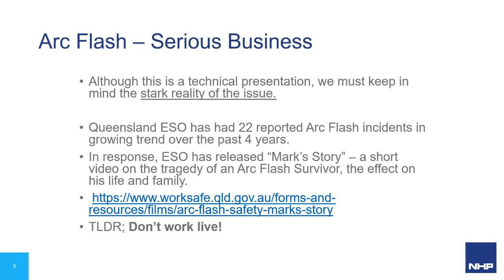It was a very avoidable incident. He was adding a power analyzer to a live switchboard. He did a lot of things wrong and he acknowledges that now, but it's not anything that we haven't seen from electricians out there in our own world. So really the message that they're pushing there is don't work live. We'll go into that in a little bit more detail later, but it is a serious issue and it does result in deaths. Queensland ESO put this together mainly because they've seen a growing increase in arc flash incidences. They've had 22 reported arc flash deaths and injuries over the last 4 years, which they're really worried about seeing.